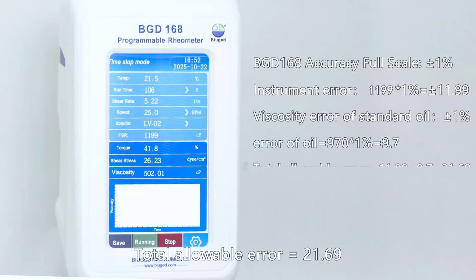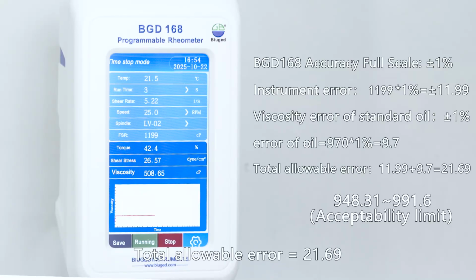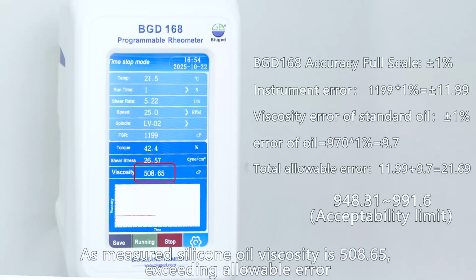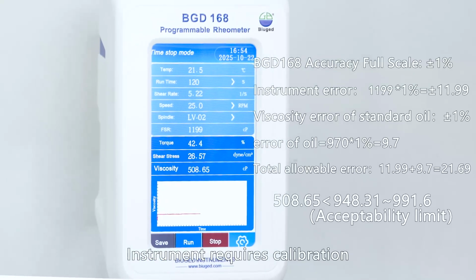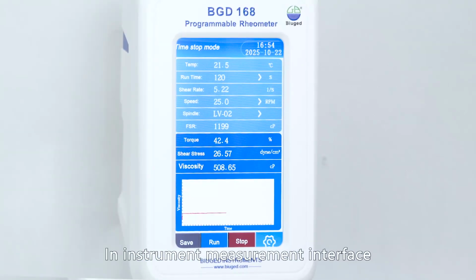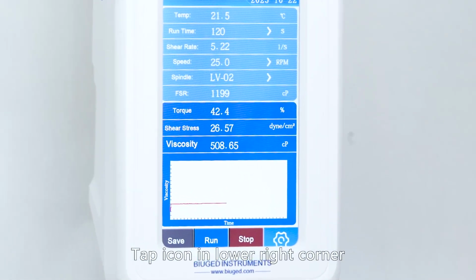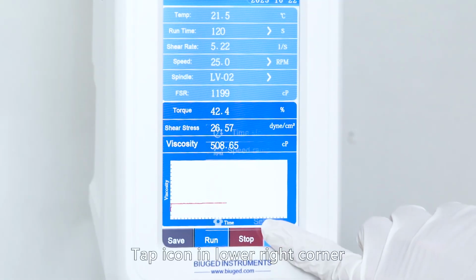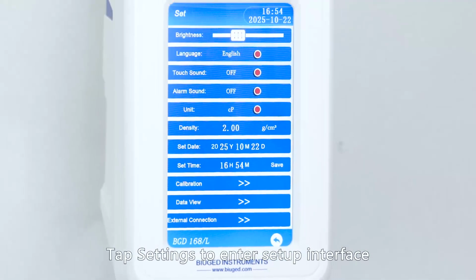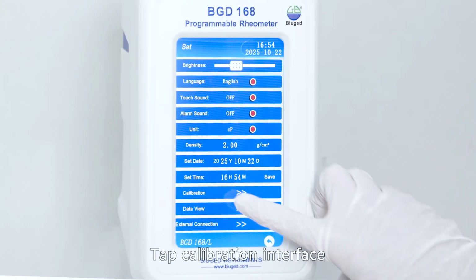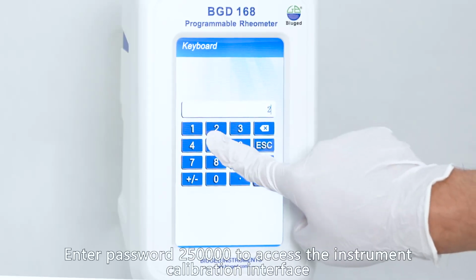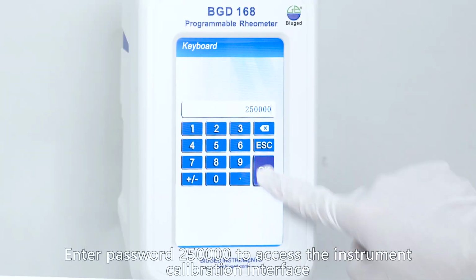Total allowable error equals 21.69. As measured, silicone oil viscosity is 508.65, exceeding allowable error. Instrument requires calibration. In instrument measurement interface, tap icon in lower right corner. Tap settings to enter setup interface. Tap calibration. Enter password 250,000 to access calibration interface.